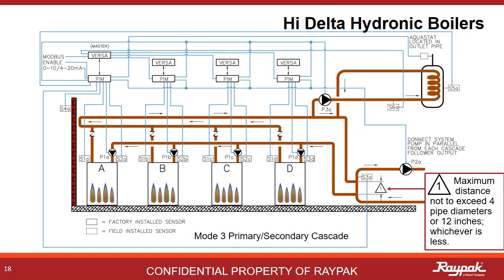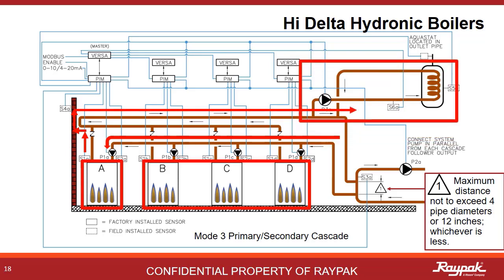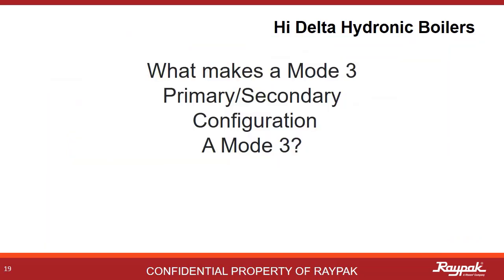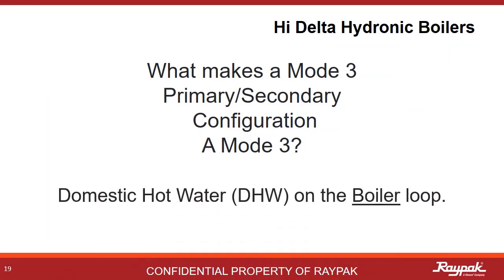Mode 3 can also be run in cascade. Here the A boiler is the master boiler and the others are followers. Being a multiple boiler cascade system, reverse return plumbing logic applies. It is a Mode 3 because the indirect domestic hot water system is on the boiler loop. What makes a Mode 3 a Mode 3 is that it must be plumbed primary-secondary and must have an indirect domestic hot water system on the boiler loop.